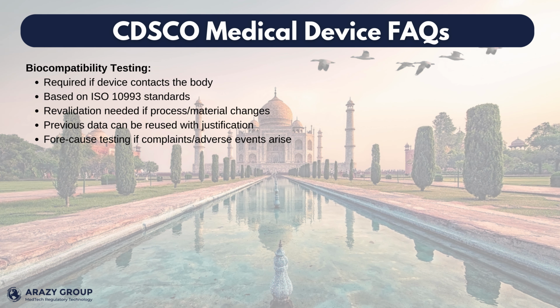A common query concerns the requirement for biocompatibility testing. CDSCO has clarified that such testing is mandatory only for devices with body contact and must be conducted in accordance with ISO 10993 standards. Existing data may be reused if generated for a similar device, provided the material, supplier, and manufacturing process are identical, supported by a justification and biological risk assessment. Any change in supplier, material, or process necessitates revalidation. In addition, complaints or adverse events require fresh for-cause testing.